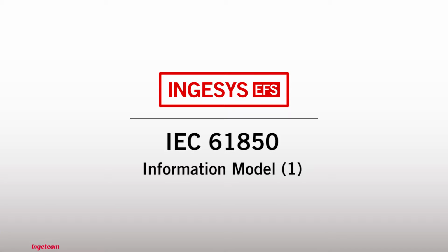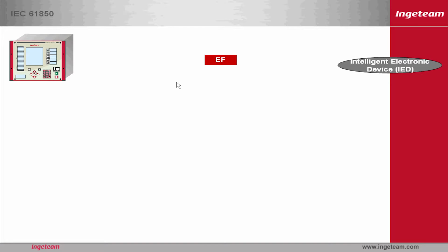A device that complies with the IEC 61850 standard is called an Intelligent Electronic Device, or IED. This device has an information model which is perfectly organized into a tree structure with a root, which is the IED itself. This device also has a name. In the example that you're going to see, it's called EF, so this will be the name that is shown in the root of its information model.